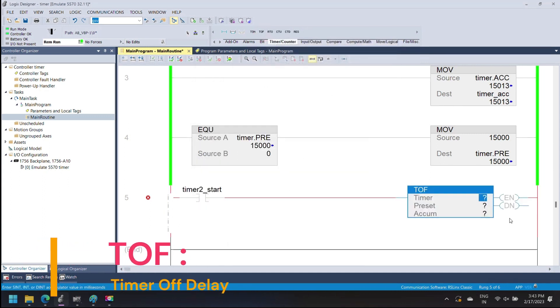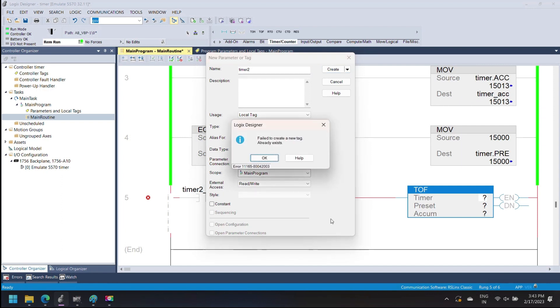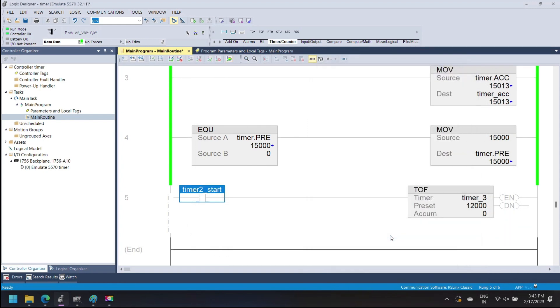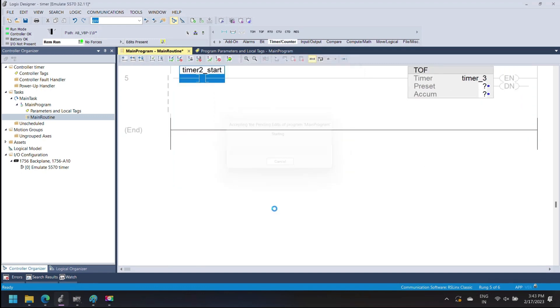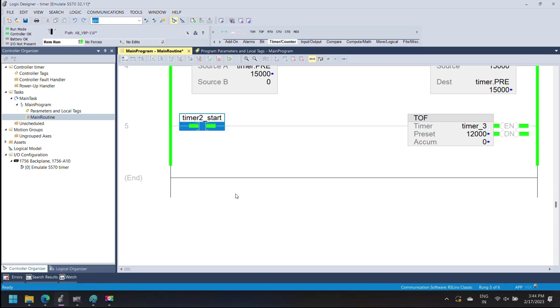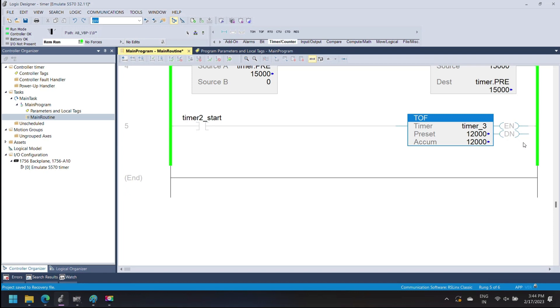Now I am adding a Timer Off Delay. Timer Off Delay starts when the input bit of the timer changes from true to false, and runs until it reaches the preset value. The accumulator value accumulates the timer value. When the timer accumulator value is equal to or greater than the preset value, the timer stops running and the timer done bit is set to false. As you can see, when the input is true the timer does not start — when the input changes from true to false, the timer operation starts. When the timer accumulator reaches the preset value, the timer done bit is set to false and the timer operation is completed.